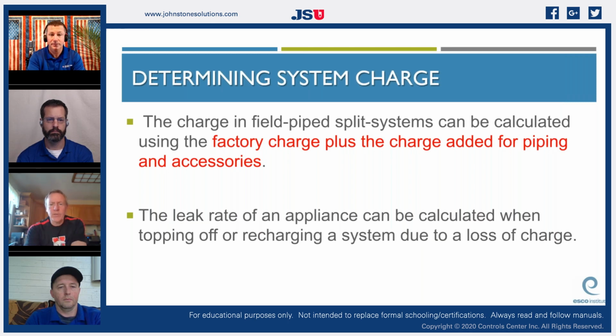Just a quick calculation on 3 ounces per 5 feet after 15 feet. Yep. So if you're a tech on the job and you're trying to figure the total factory charge plus the charge added, just if you can measure the length of the line set. Actually, I had a call on that yesterday in an apartment. We said, I can't find where all the line set went. I said, don't worry about it.